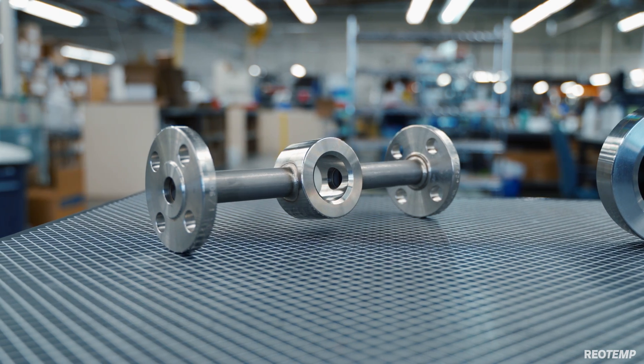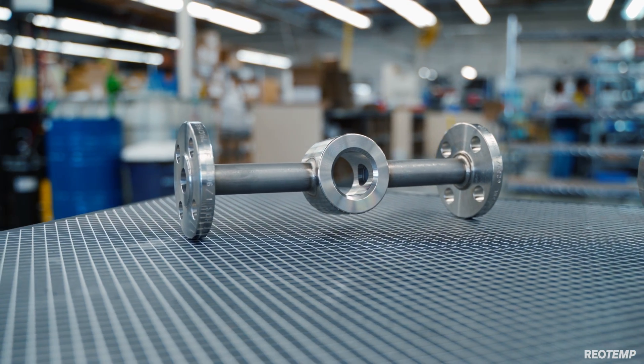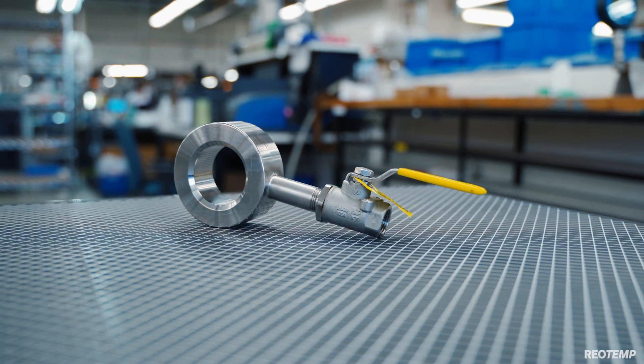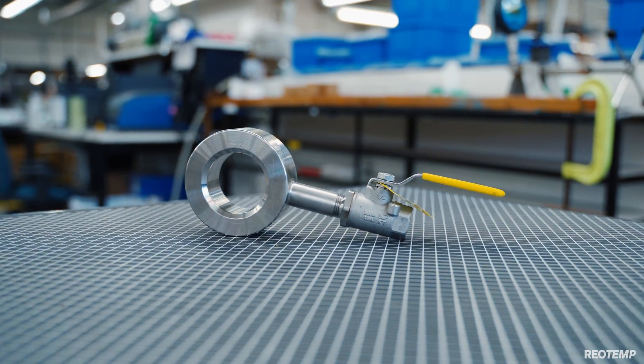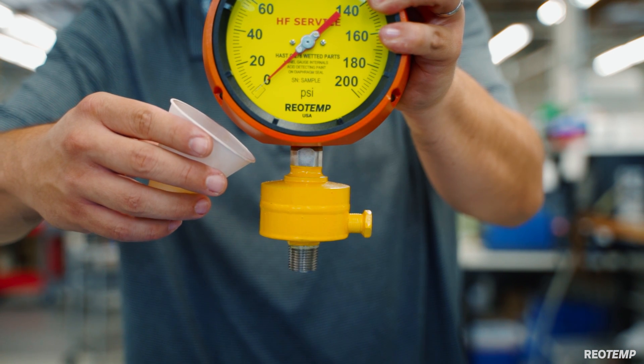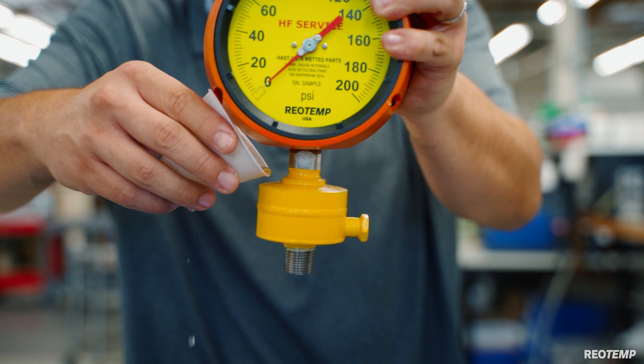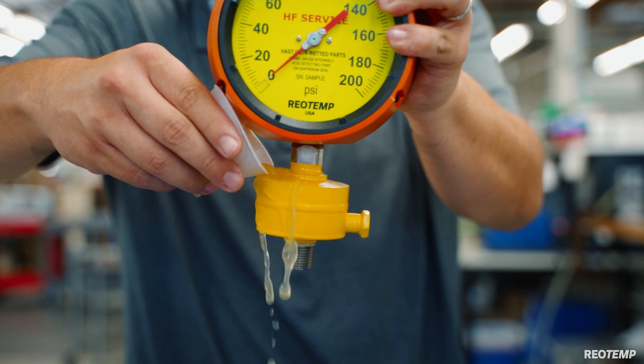Rheotemp also provides flushing rings and isolation valves in Monel 400, Hastelloy C276, or whatever metallurgy your site requires. The unit comes standard with an acid-detecting paint. Should a leak occur and the process fluid has a pH of 3 or lower, the yellow paint will change color to a bright red.